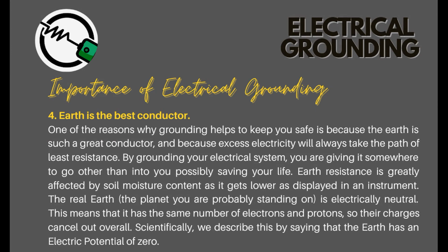4. Earth is the best conductor. One of the reasons why grounding helps to keep you safe is because the earth is such a great conductor, and because excess electricity will always take the path of least resistance. By grounding your electrical system, you are giving it somewhere to go other than into you, possibly saving your life. Earth resistance is greatly affected by soil moisture content, as it gets lower as displayed in an instrument. The real Earth, the planet you are probably standing on, is electrically neutral. This means that it has the same number of electrons and protons, so their charges cancel out overall.